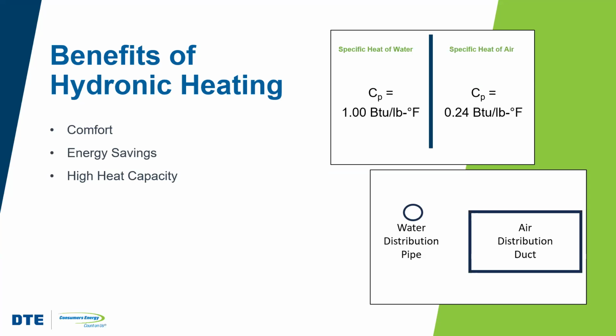So this means that the material that conveys the water, that piping, right, can be a lot smaller than the ductwork that has to convey that air, because we need a lot less water, right? So there's right there some additional savings, right? You've got material first cost and labor installation costs, right? So there you've got some savings in that, particularly on the material side, right? When we look at the first cost for ductwork, it's usually about twice the cost of copper piping, 13 times the cost of PEX on a per foot basis, right?